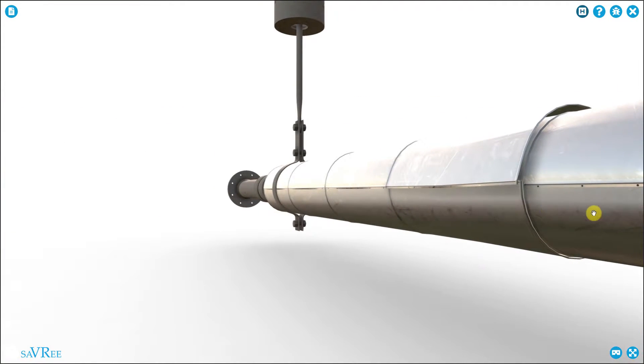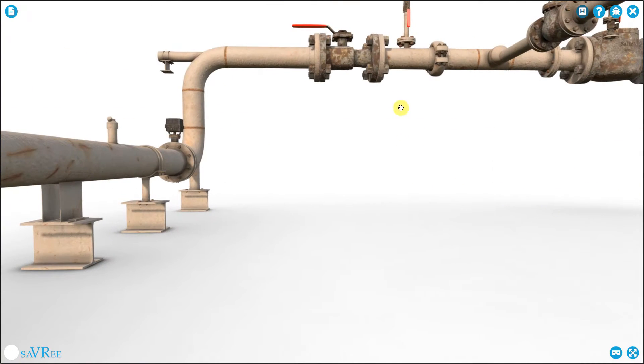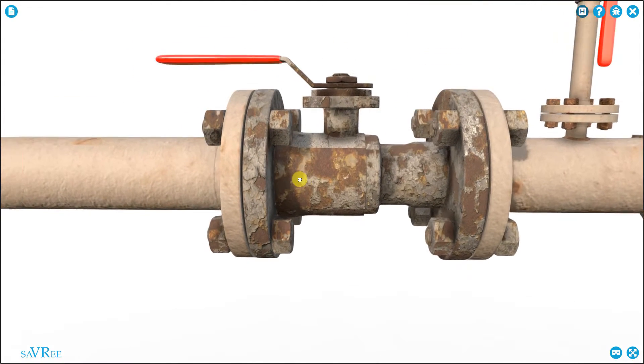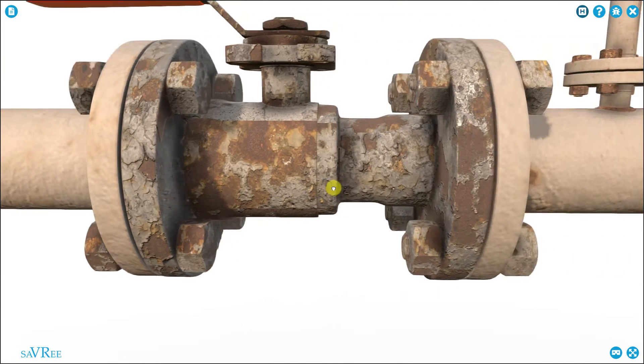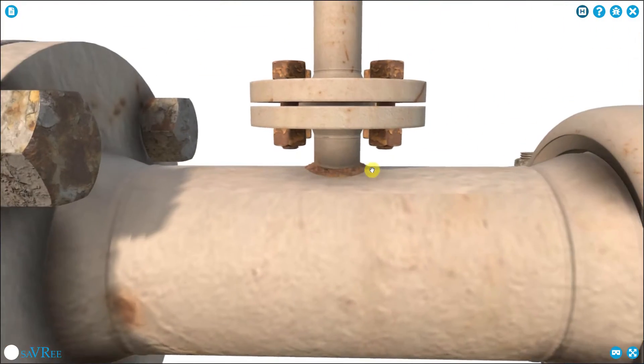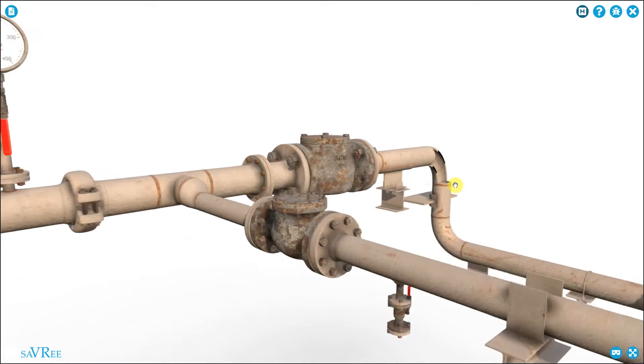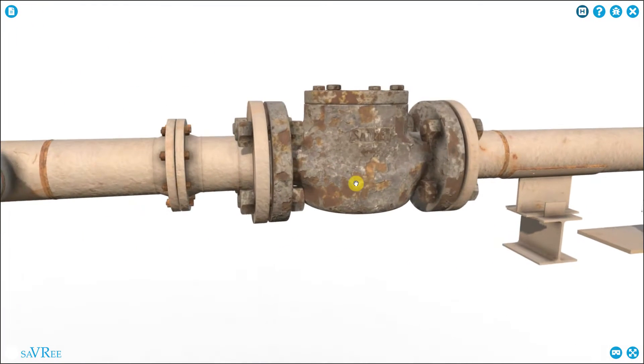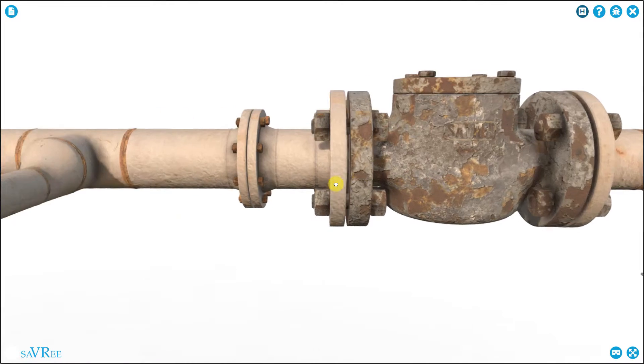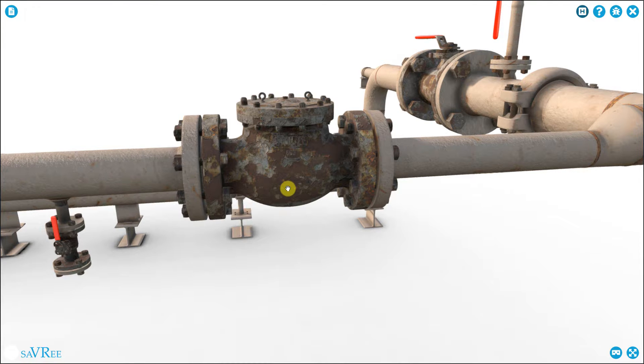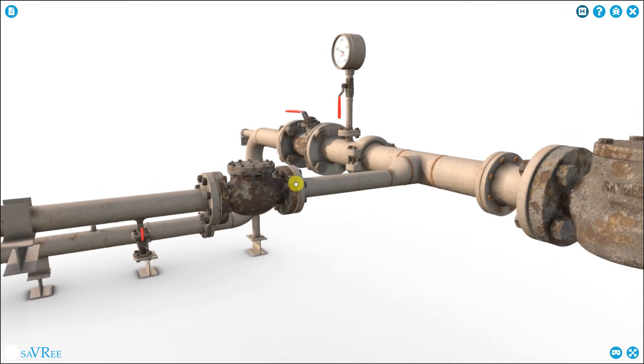If we look around the piping system, you'll see that there are other flanges as well. We can zoom in on a few. This ball valve is joined to the piping system via flanges — here is one flange and here is the other. But if you look over here, we've got a smaller flange. And if we change our view a little bit, you can see that there are other components within the piping system that also require flanges. Flanges allow us to install components within the piping system. These components might be valves, they might be steam traps, they might be strainers, or anything else that we need to connect to the piping system in order to make it work as we desire.